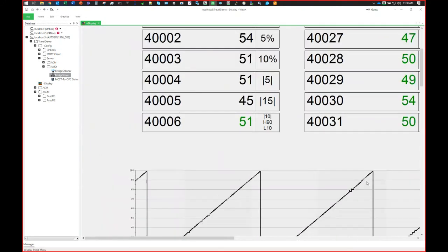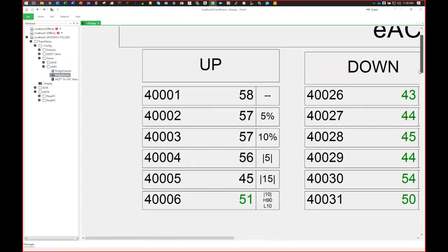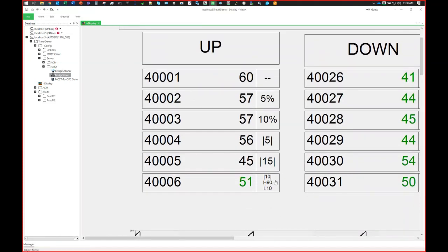He has a deadband of 10, but also 2 trigger points, right, of 90 and 10. So he will update by 10. So he'll update again at 71. There we go. And then 81. And then when his value on the device hits 90, he's going to go into the high trigger state. This is not an alarm for legal purposes, but it basically will drop his deadband and he'll update every time he changes value, as we'll see now.